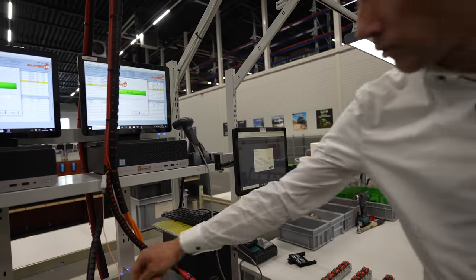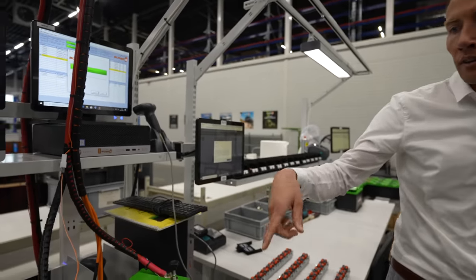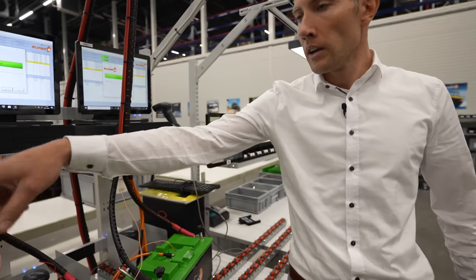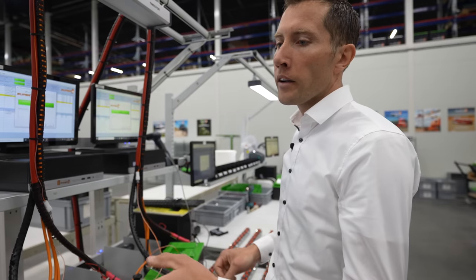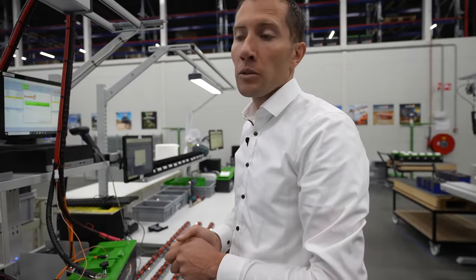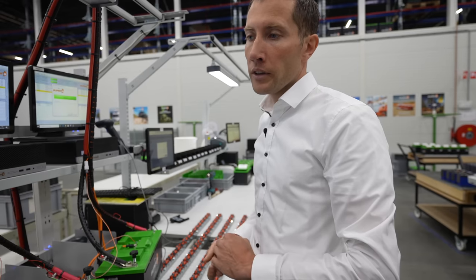The bus connections use an orange cable connector. The Nomada battery, used in the largest systems, has three connectors — one to connect to another battery, one you can wire through, and a third required by DNV, the maritime commercial type approval. DNV requires a BMS-independent temperature sensor. So even if all temperature sensors on the entire BMS would fail, this third connector provides an additional temperature sensor, because DNV considers temperature control critical on board ships.